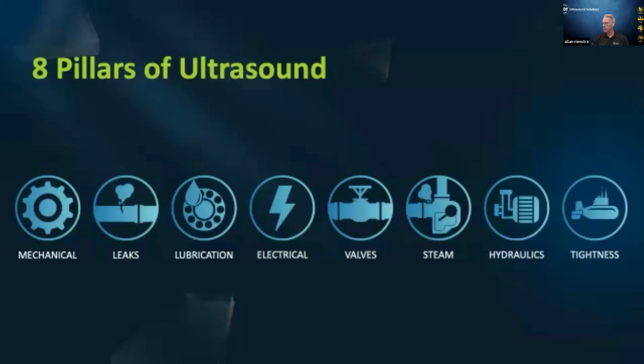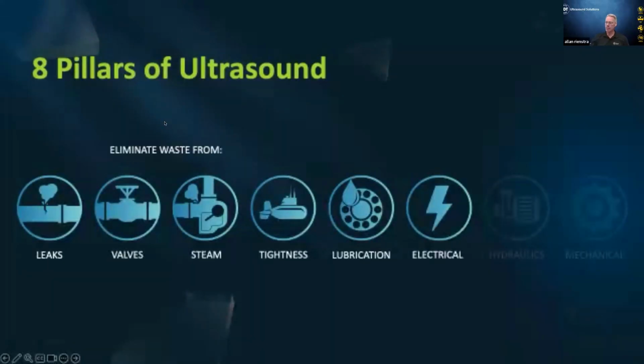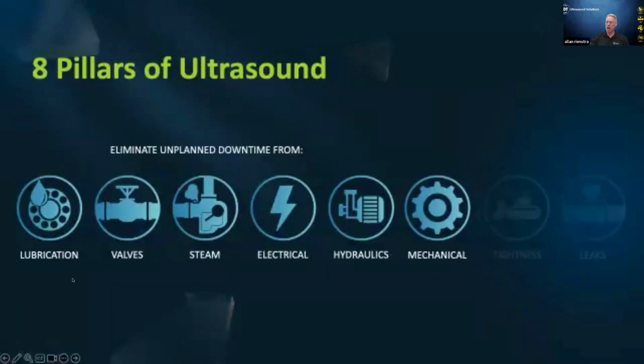And if we look at classifying these, the first 4, leaks, valves, steam, and tightness, help us eliminate or control waste. And if we look at lubrication, valves, steam, electrical, hydraulics, and mechanical, by doing ultrasonic surveillance on these asset categories, we can eliminate unplanned downtime.